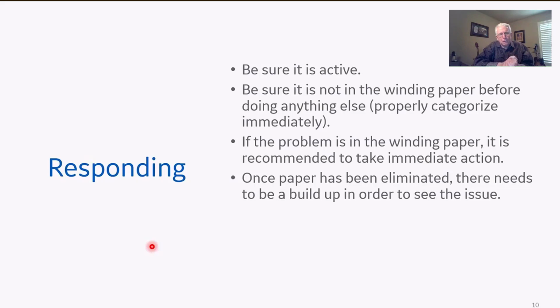So I have a bushing out there. I'm running an offline power factor on this bushing, and it was 0.6%. Now it's 1.9%. Okay? And so I look at that. And so that capacitor went from 0.6 to 1.9. When is it going to fail? When should I take this bushing out of service?